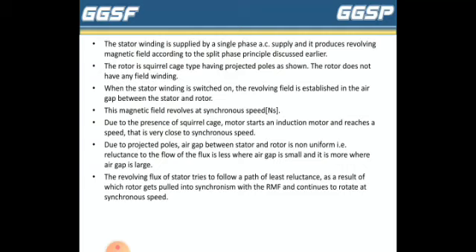When the stator winding is switched on, the revolving field is established in the air gap between the stator and the rotor. This magnetic field revolves at the synchronous speed, that is Ns. Due to the presence of the squirrel cage, the motor starts as an induction motor and reaches a speed very close to synchronous speed. Due to salient poles, the air gap between stator and rotor is non-uniform, that is, reluctance to the flow of flux is less when the air gap is small and more where the air gap is large. The revolving flux of the stator tries to follow the path of least reluctance, as a result of which the rotor gets pulled into synchronism with the RMF and continues to rotate at synchronous speed.